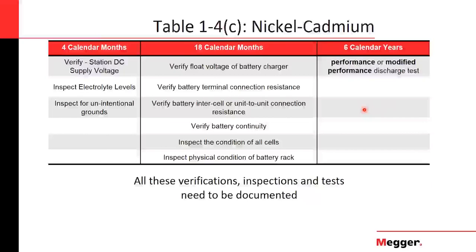Okay, the next table is table 1.4c, and this is for nickel cadmium. These are also batteries that use liquid electrolyte. You can see through the jars, so you are asked to inspect the electrolyte level and the same other 2 inspections that are required for the 4 calendar months. The same 18 calendar month schedule of testing. The point to highlight here is that in this one, no ohmic values are required. The reason is that NiCad batteries behave differently. The electrolyte that they have is alkaline. This material is not dissolved in the liquid, it's mainly in the plates. So you really won't see any ohmic value change throughout the life of the battery. And you might see a big change at the end of the life of the battery, or you might not.